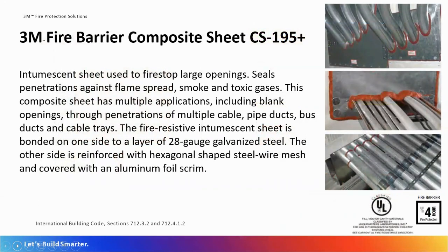This next product is our composite sheet, CS 195 Plus. This is one of the most cost-effective ways to close down a large opening in a fire-rated wall. It can also be used in a floor assembly, but just mind you, this is not a load-bearing situation. So any situation where you would use this in a floor and you're going to have any kind of pedestrian traffic, it would need to be protected from that. So basically what it is, it's an intumescent sheet that is sandwiched on one side with 28 gauge galvanized steel, and on the back side, it's a foil scrim system.